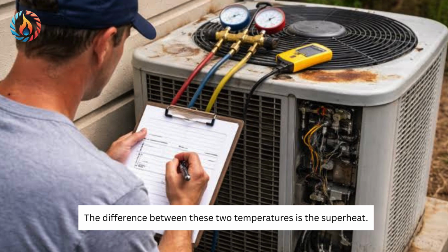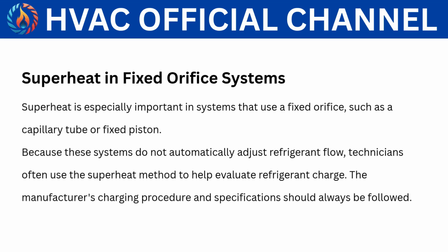Superheat in fixed orifice systems. Superheat is especially important in systems that use a fixed orifice, such as a capillary tube or fixed piston. Because these systems do not automatically adjust refrigerant flow, technicians often use the superheat method to help evaluate refrigerant charge. The manufacturer's charging procedure and specifications should always be followed.